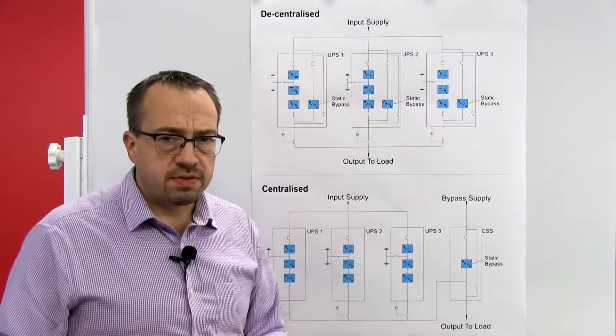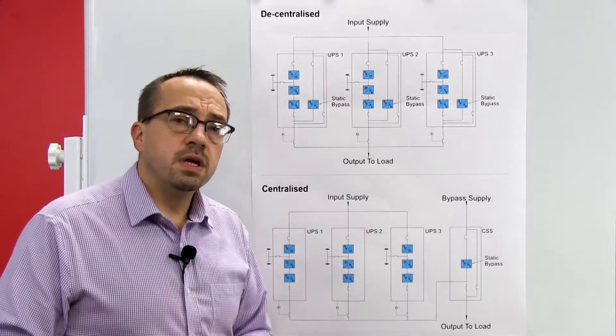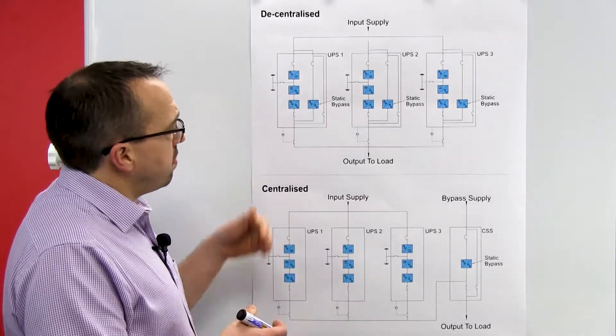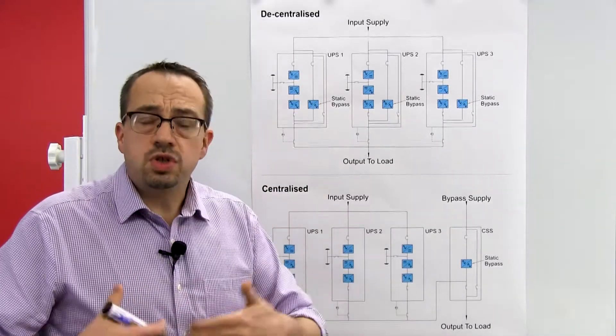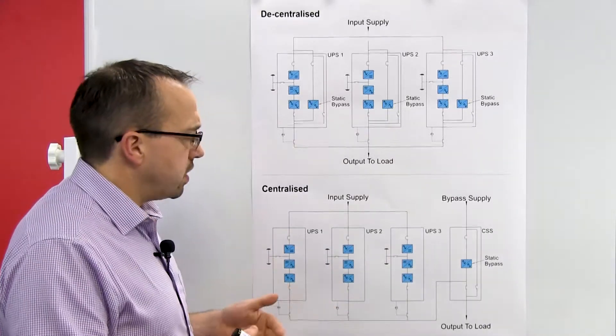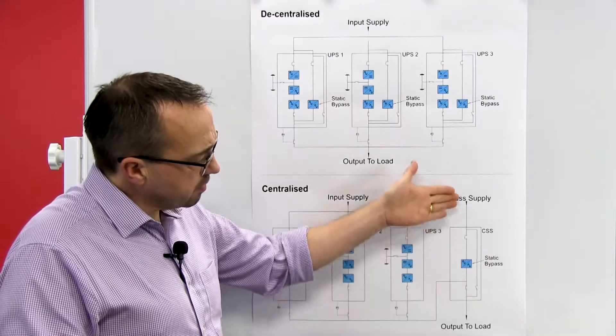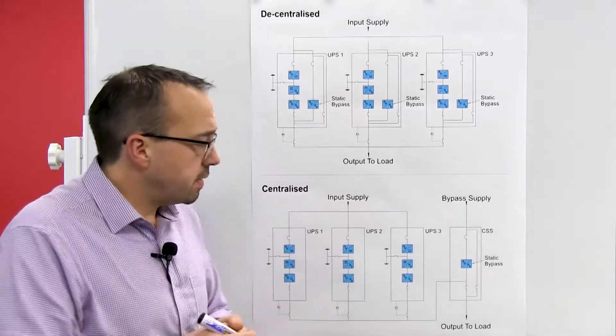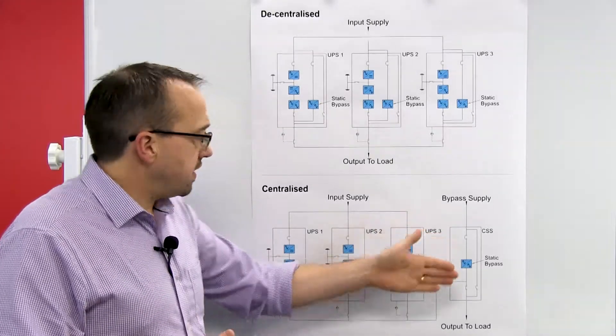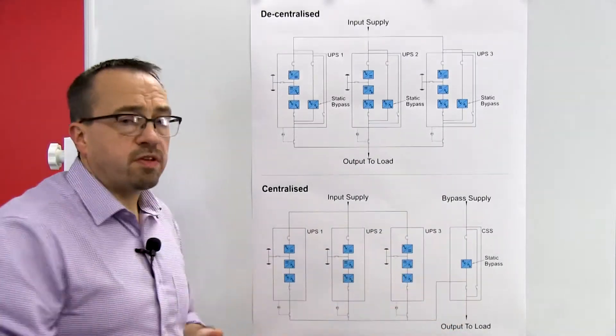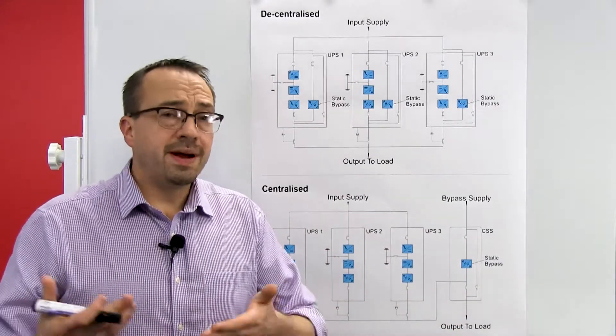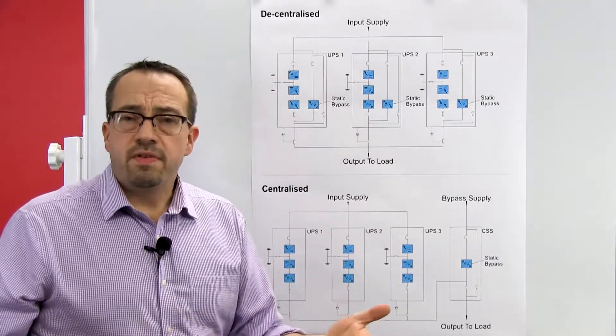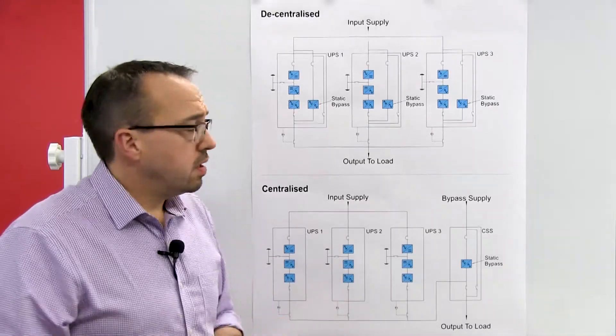The next consideration is resilience, which breaks down into two areas. In terms of operational resilience, both systems are in most cases just as reliable and resilient as each other. However, some people consider the single bypass module in a centralized system to be a potential single point of failure — which it is. Adding a second bypass module to remove that single point of failure would simply mimic the decentralized approach and would be a very cost-prohibitive method of installation.